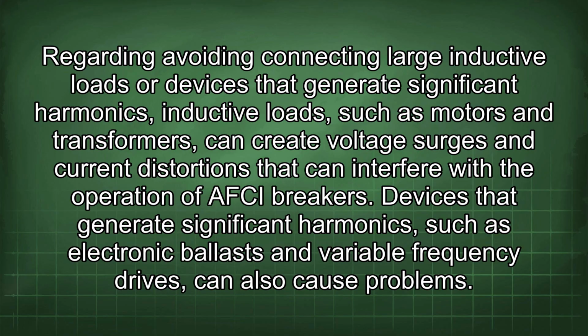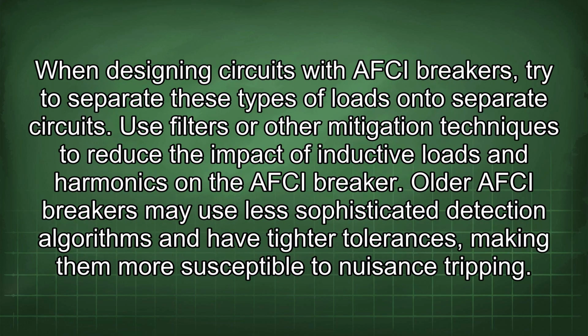Regarding avoiding connecting large inductive loads or devices that generate significant harmonics, inductive loads, such as motors and transformers, can create voltage surges and current distortions that can interfere with the operation of AFCI breakers. Devices that generate significant harmonics, such as electronic ballasts and variable frequency drives, can also cause problems. When designing circuits with AFCI breakers, try to separate these types of loads onto separate circuits. Use filters or other mitigation techniques to reduce the impact of inductive loads and harmonics on the AFCI breaker.